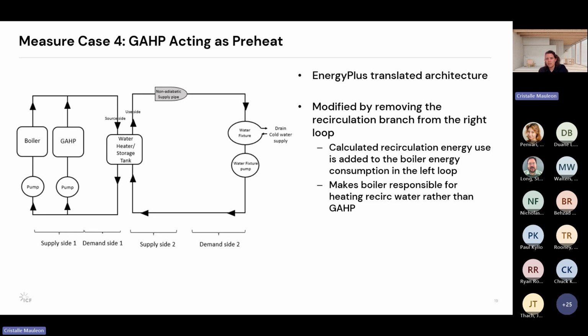This slide shows the EnergyPlus architecture for measure case 4, where the gas absorption heat pump is used to preheat city water only, while the boiler handles recirculation water. This configuration is simplified because the recirculation branch is removed from the right loop, and instead the calculated recirculation energy use is added to the boiler's load on the left loop.